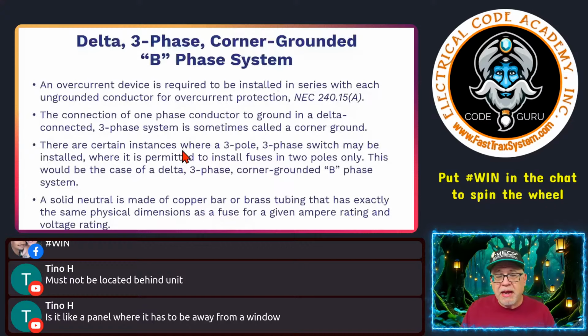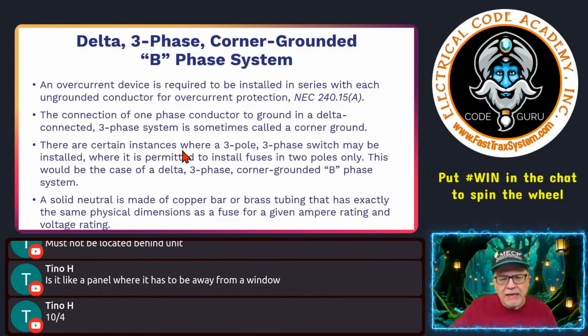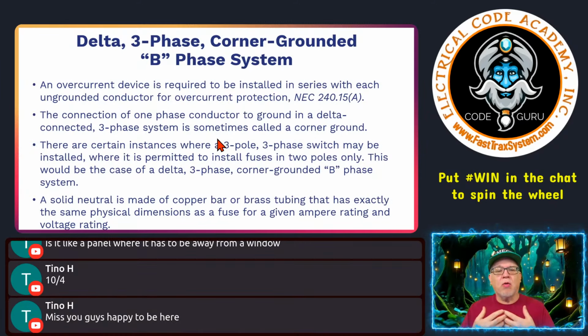So in your career, you may run into a delta system, right? You may run into a three-phase corner-grounded delta B-phase system. All right, so it says an overcurrent device is required to be installed in series with each ungrounded conductor for overcurrent protection. Okay, so if I have conductors coming in, then I have an overcurrent device that has to be installed in each one of those ungrounded conductors to provide overcurrent protection based on 240.15(A).